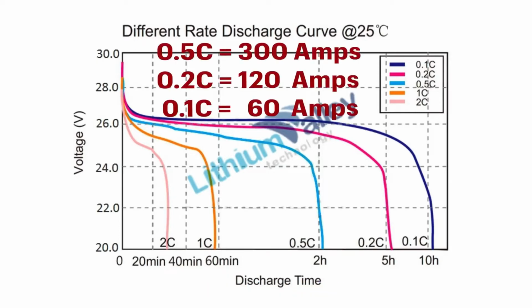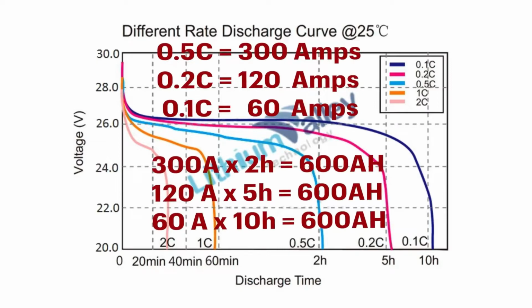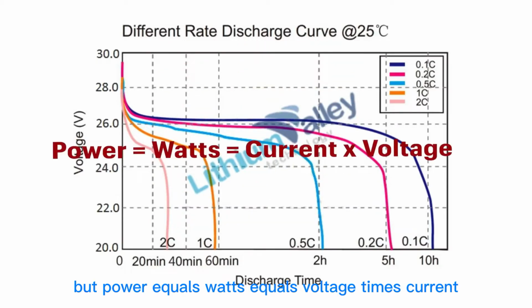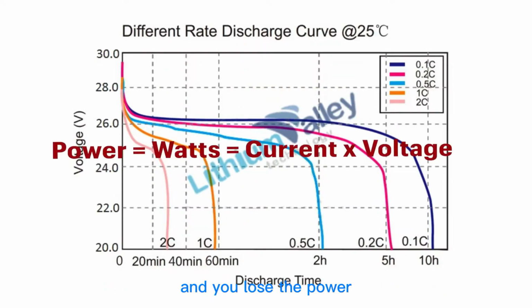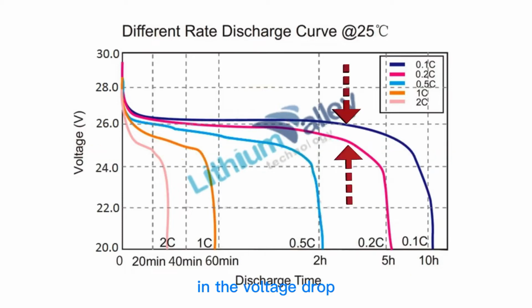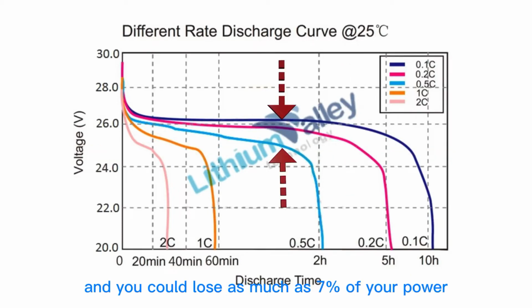Looking at my system, if we do the math, they all come up 600 amp hours. But power equals watts equals voltage times current, and you lose the power in the voltage drop. The higher the current, the larger the voltage drop, and you could lose as much as 7% of your power.